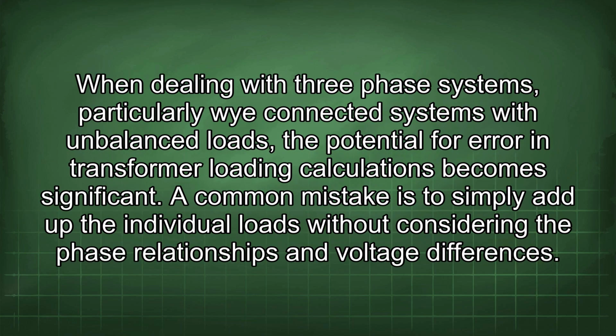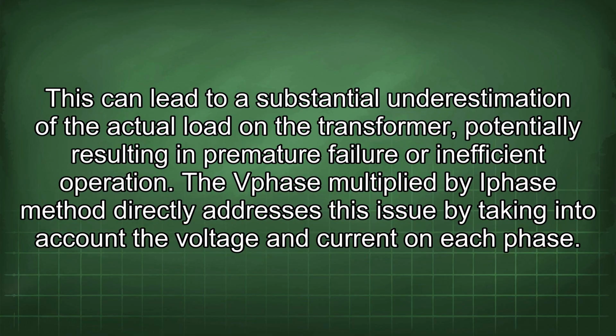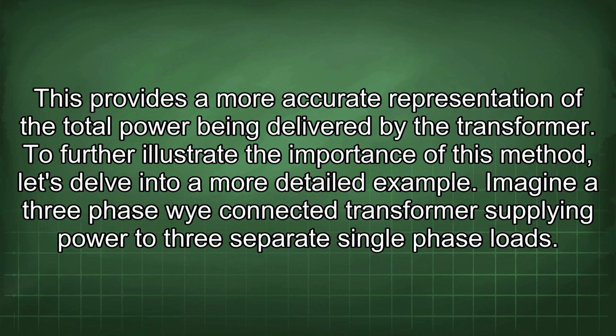When dealing with three-phase systems, particularly Y-connected systems with unbalanced loads, the potential for error in transformer loading calculations becomes significant. A common mistake is to simply add up the individual loads without considering the phase relationships and voltage differences. This can lead to a substantial underestimation of the actual load on the transformer, potentially resulting in premature failure or inefficient operation. The Vphase multiplied by Iphase method directly addresses this issue by taking into account the voltage and current on each phase. This provides a more accurate representation of the total power being delivered by the transformer.